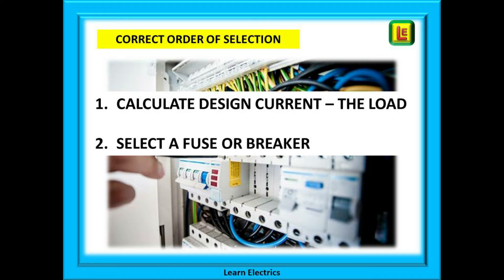Next we will select a fuse or circuit breaker that will take at least that amount of current. Any smaller and the breaker will continually nuisance trip. But neither must the breaker be of such a great size that it will never operate. It should be the same as or just above the maximum design current. The breaker size uses the symbol IN for nominal current rating — think of it as N for the number printed on the breaker. A 32 amp breaker has an IN of 32 amps.